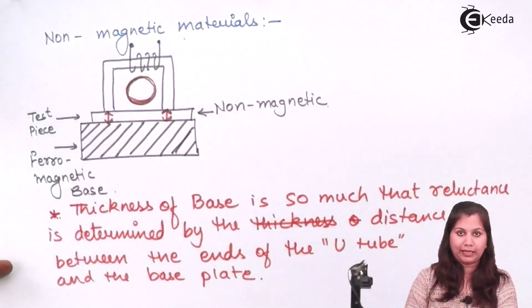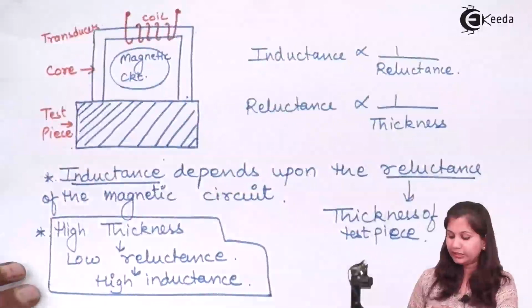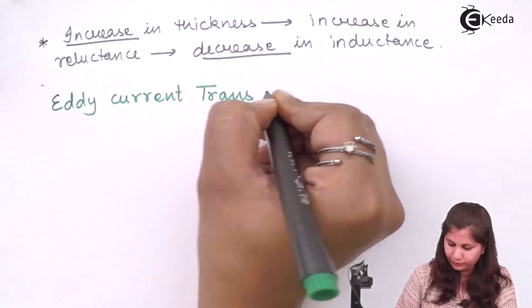Another arrangement is similar. This is the coil, this is the core, and this is the test piece, which is a non-magnetic material. This non-magnetic material is placed on a magnetic base, and this ferromagnetic base is so thick that the reluctance of the magnetic circuit is determined by the distance between the ends of the U tube.